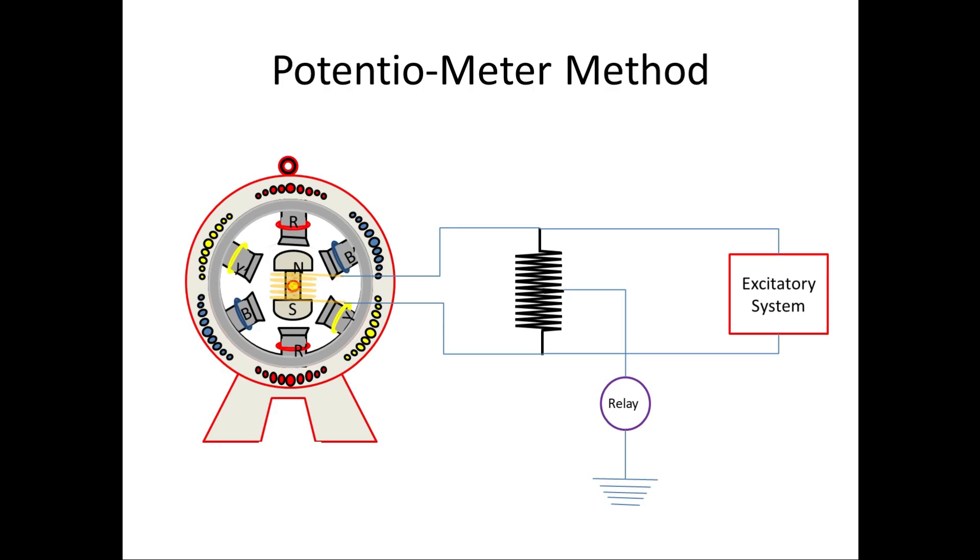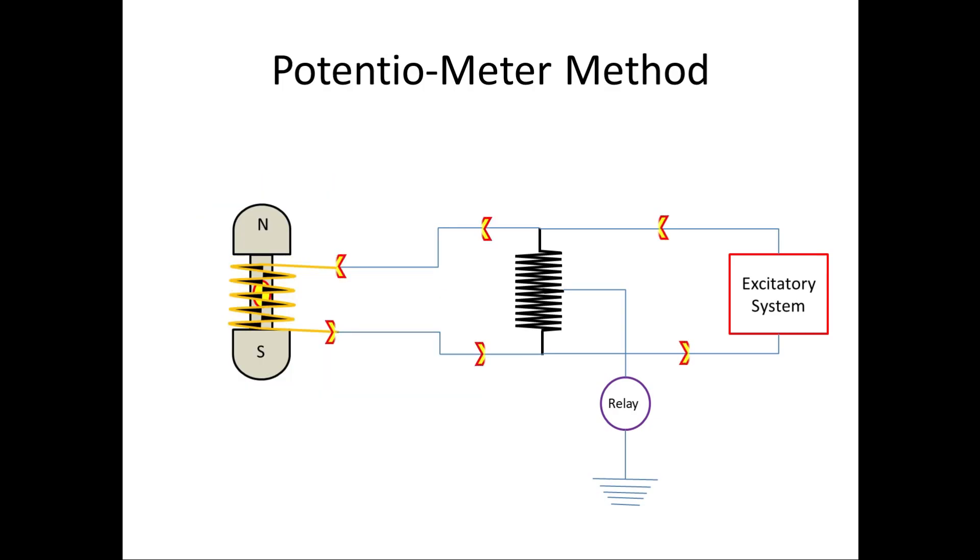If you see the construction of this method, the circuit is parallel between the rotor coil and exciter. A high resistor is connected, and from this high resistance the center point is taken to voltage relay through grounding.